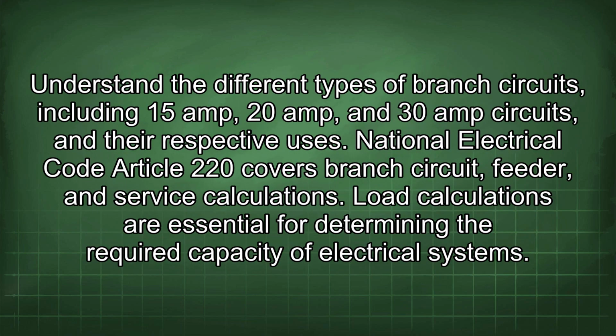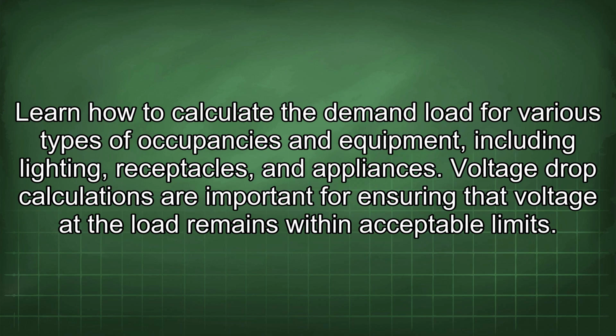Understand the different types of branch circuits, including 15 amp, 20 amp, and 30 amp circuits, and their respective uses. National Electrical Code Article 220 covers branch circuit, feeder, and service calculations. Load calculations are essential for determining the required capacity of electrical systems. Learn how to calculate the demand load for various types of occupancies and equipment, including lighting, receptacles, and appliances.